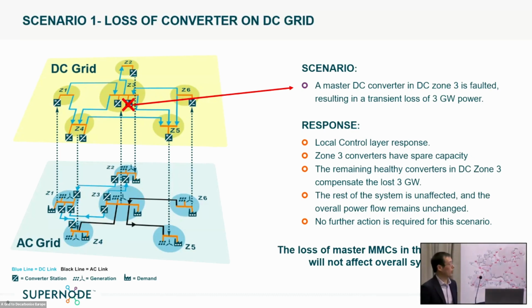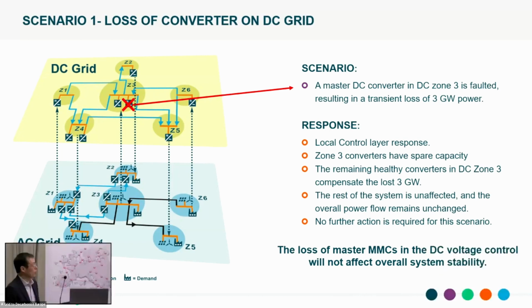The consequence of losing this single converter means that the transmitted power through this converter before the contingency can actually be picked up by the rest of the healthy converters in DC zone three very quickly, within milliseconds. The overall response of the system means the power will simply be shifted from this converter to the rest of the healthy converters in DC zone three.